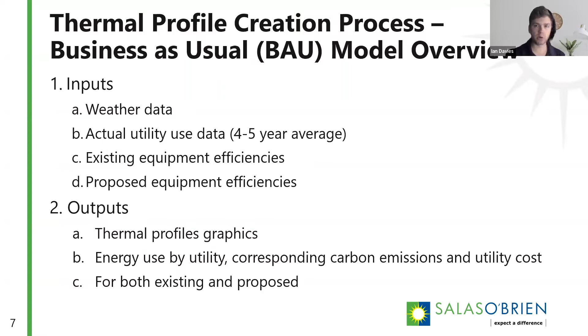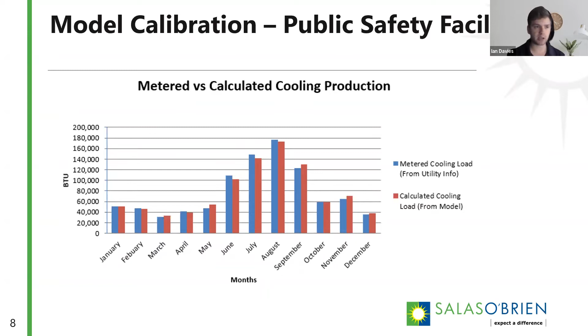In order to make sure our model is working correctly, we calibrate it. We do this by taking the actual metered information, shown in blue, and comparing it to what the model is calculating. We do this for each of our buildings, adjusting inputs and settings to make sure the annual heating and cooling energy is within 1% of each other, so the calculated result is 1% accurate in that sense. We do this for all the buildings, for both heating and cooling.